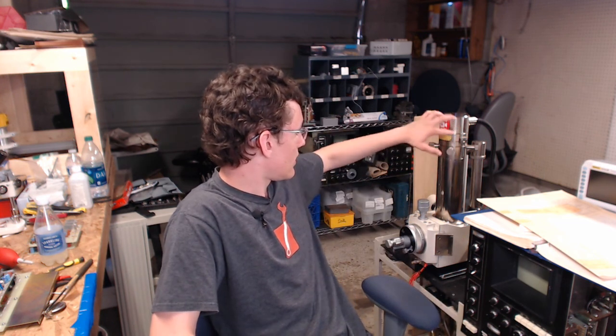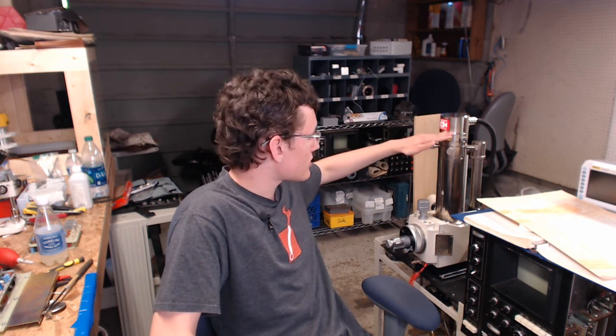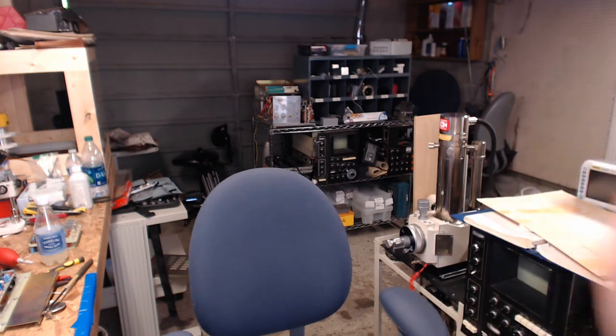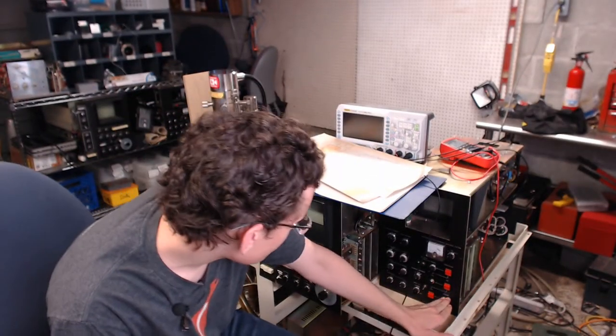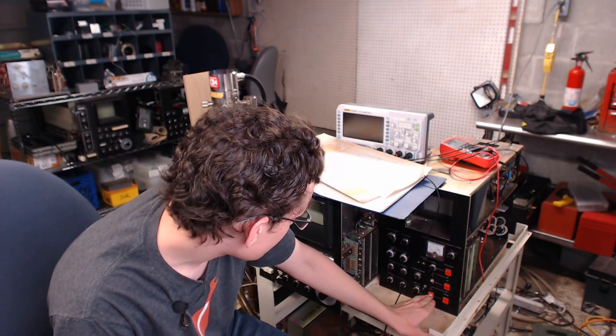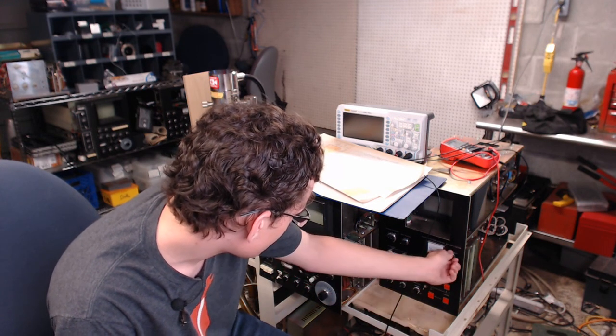The high voltage won't turn on until the columns have vacuum, because you run the risk of shorting out the electron gun, or arcing out the electron gun to the accelerating voltage. So let's get that going. Gotta plug this SEM in. Give the fan, you guys watch this. Okay, vacuum gauge alive.